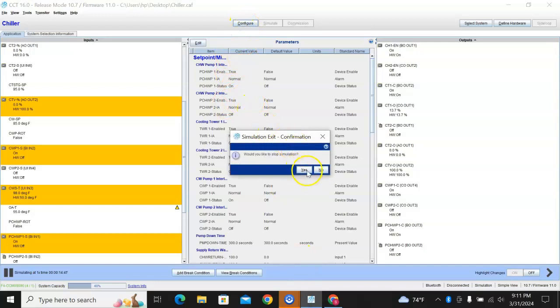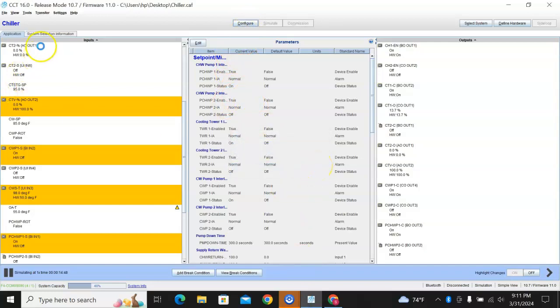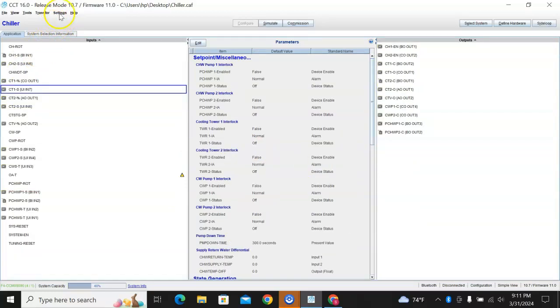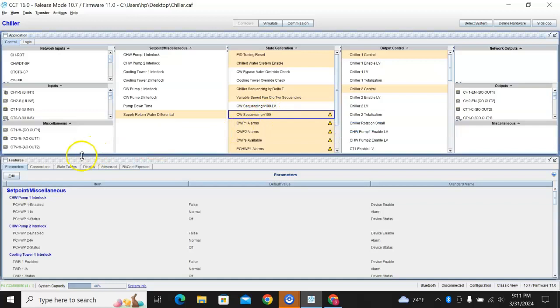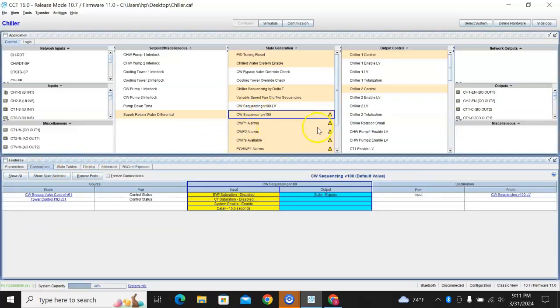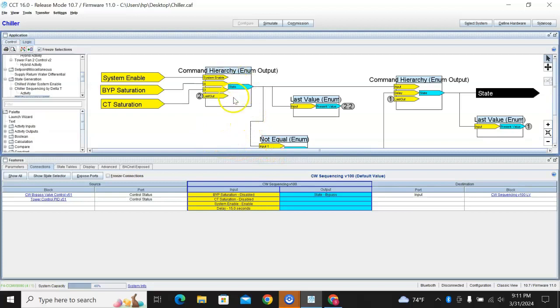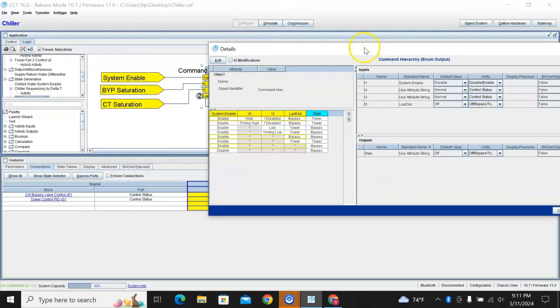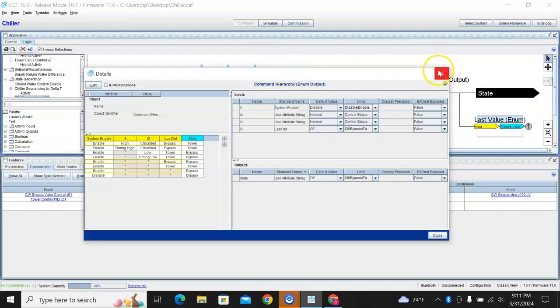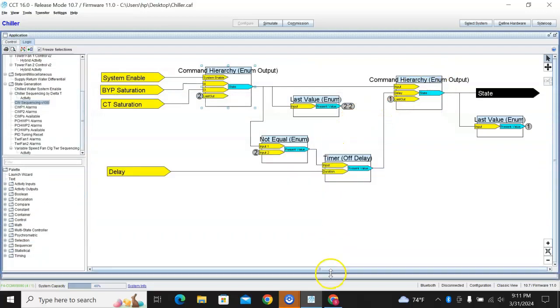So I'll reset that. I want to show you what you could fix to make this go better. We can go in, we can mess with the PID, yes, but I just don't like the way it's set up. This block right here is what's switching it between bypass mode and tower mode. And this little command hierarchy block looks at the PID saturation time between the bypass PID and the cooling tower PID, and it determines what mode it's in. I don't really like that because saturation time takes a while.